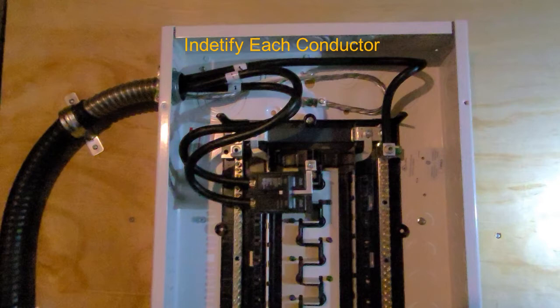Also, you notice that we used white electrical tape to mark the 3 conductors of the service cable. You need to mark the 3 conductors right after you strip the service cable, because the markings on the conductors come off really easily. I believe over a certain size of cable, they don't color code the conductors anymore. So in this case, we either use colored heat shrink on those conductors, or we simply use electrical tape to color them accordingly.